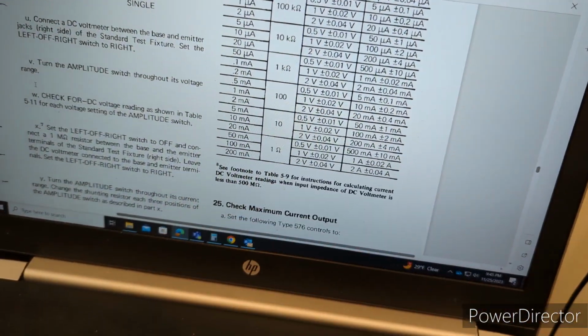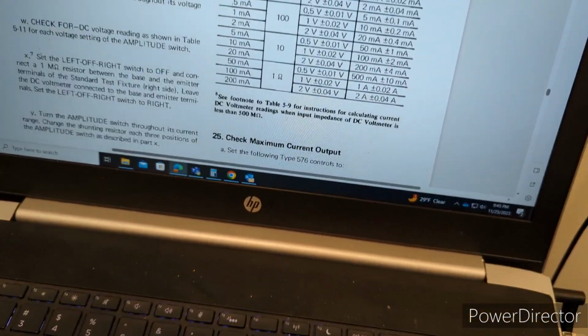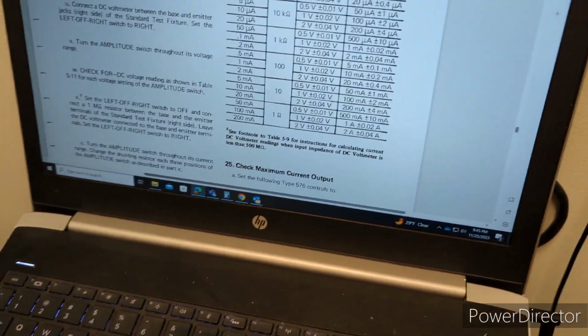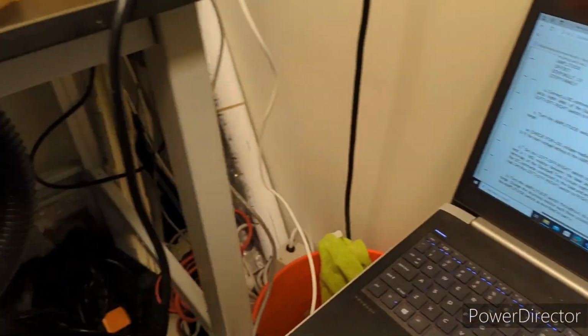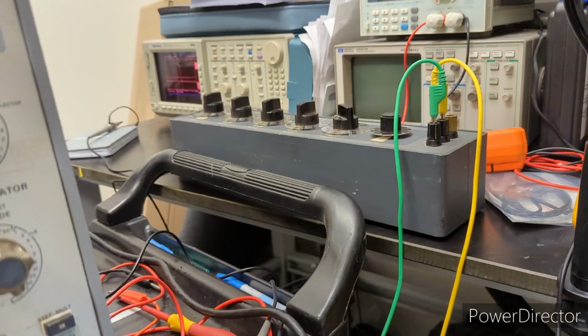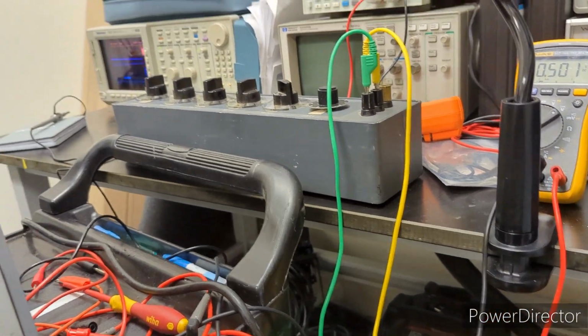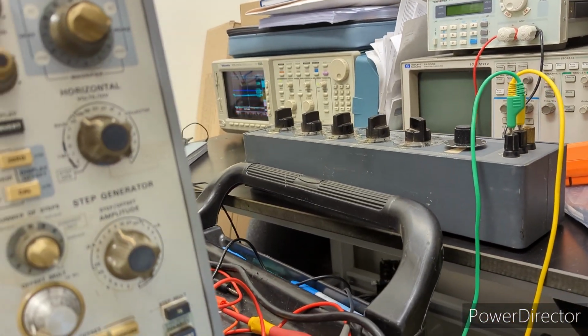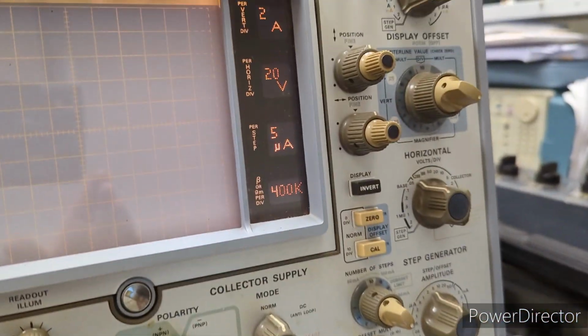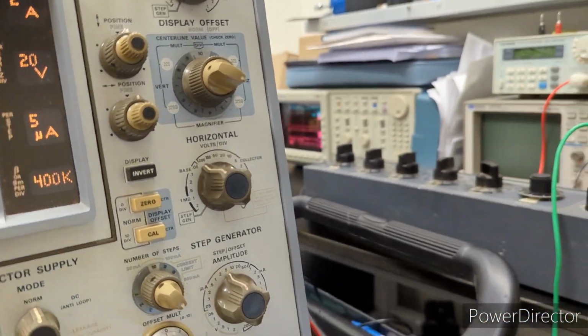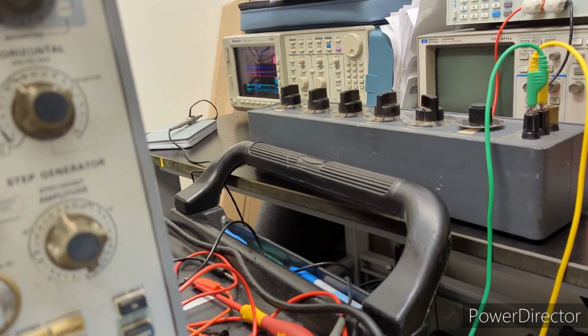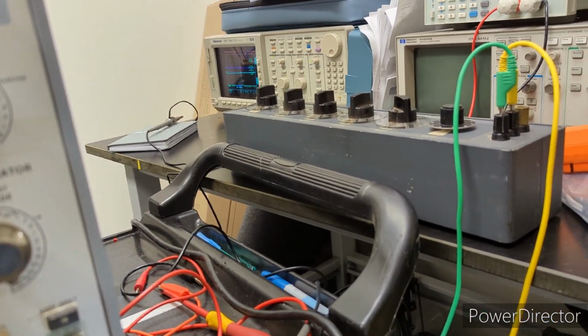All right, so I've just been going through the current settings for the amplitude switch, and everything looks really good. Now, I started at 1 ohm. For some reason, the readings just aren't very accurate at 1 ohm on the decade box, and I noticed that as well when trying to use the 1 ohm decade for a different measurement for the vertical switch. So it may not be as accurate as the other decades, or there might be something wrong with that decade, but the other ones look really good.